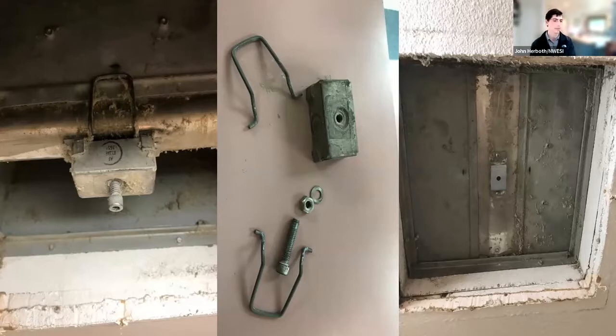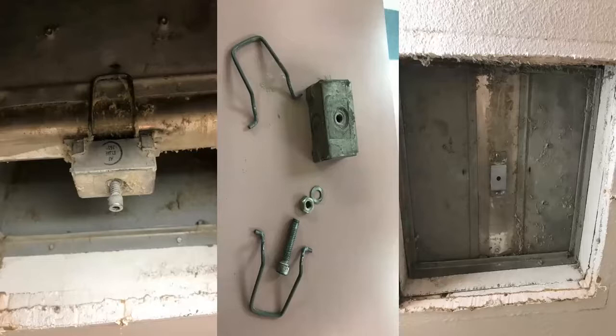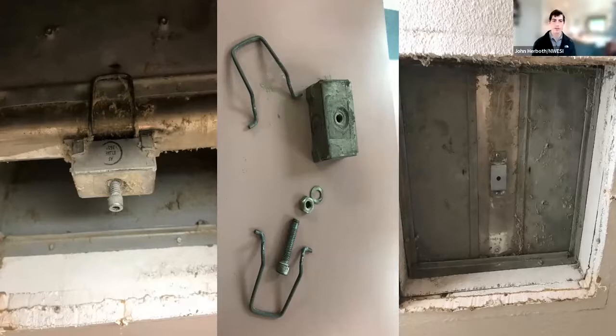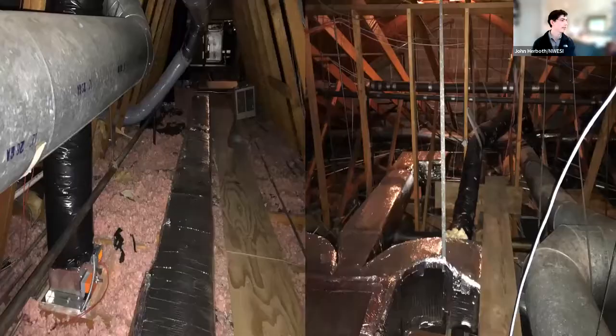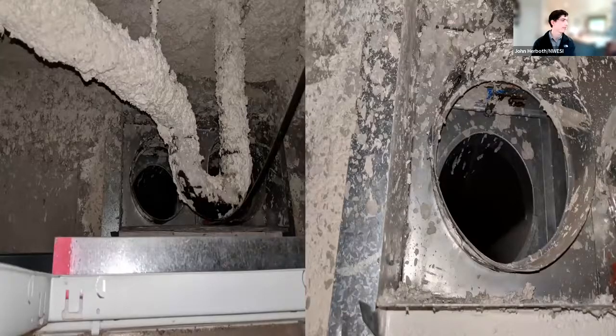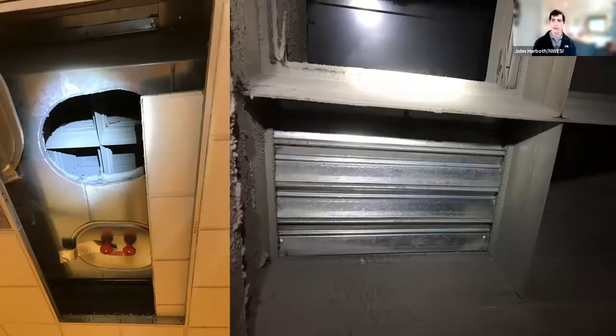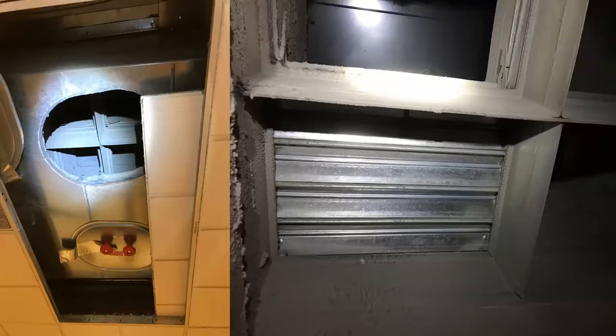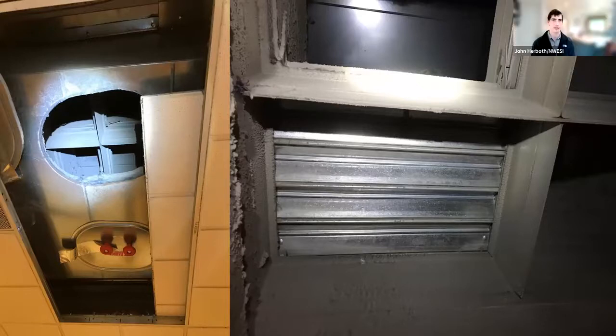Somebody had a question here: do you need to test fire dampers on the same schedule as fire smoke dampers? And that's correct. Yes, the same schedule. But Larry, you had a clarification on, was it radiant dampers? Well, ceiling radiation dampers do not need to be periodically tested. And those are going to be your fabric style. I think I might have a picture of it. Oh, I'm jumping ahead. I'll get to it. But yeah, ceiling radiation dampers don't have to be tested. I haven't really discussed that one with fire marshals, but I will take Larry at his word and I'll bring it up to my local code official and make sure that they agree.